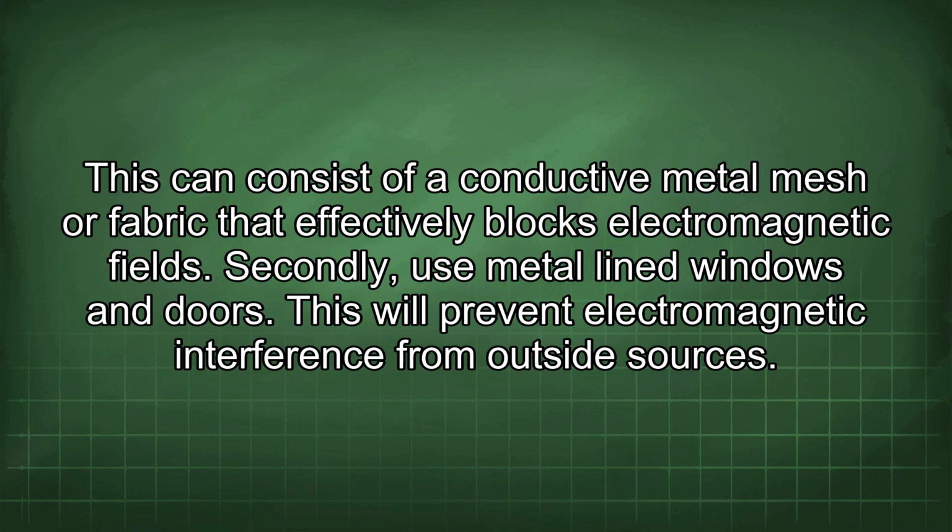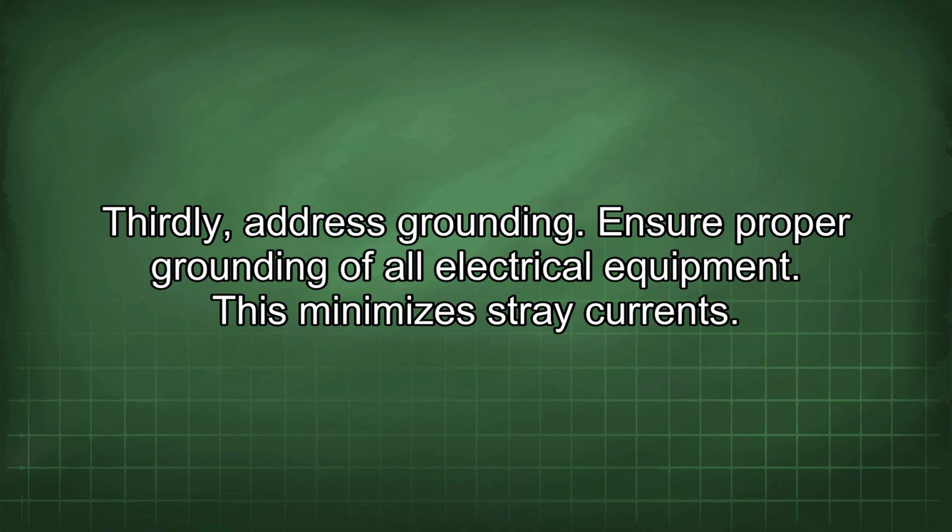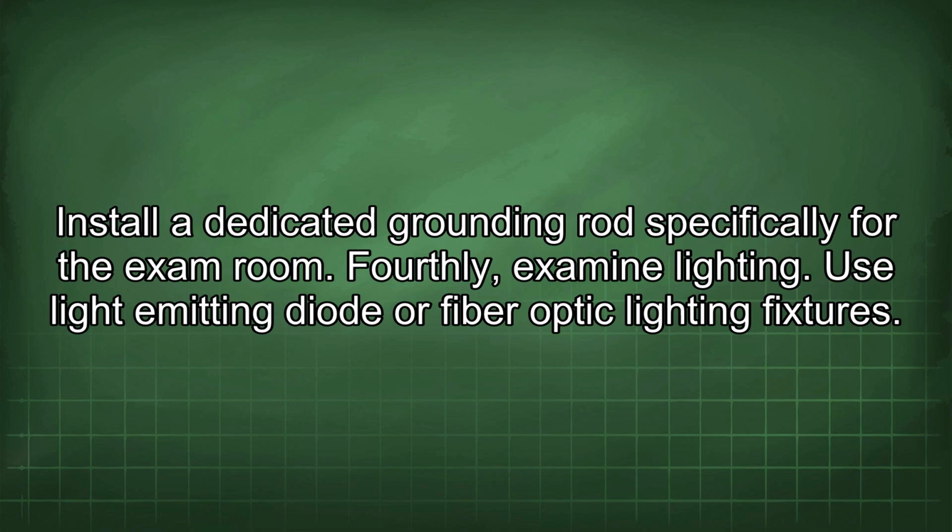Secondly, use metal-lined windows and doors. This will prevent electromagnetic interference from outside sources. Thirdly, address grounding. Ensure proper grounding of all electrical equipment. This minimizes stray currents. Install a dedicated grounding rod specifically for the exam room.